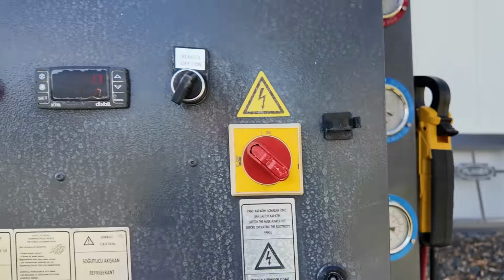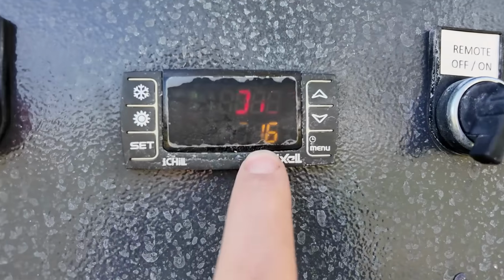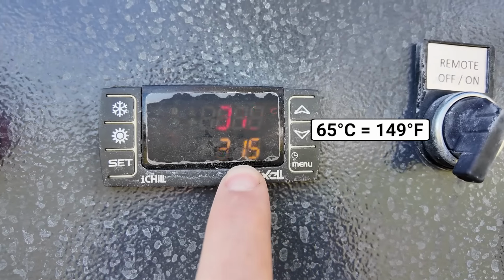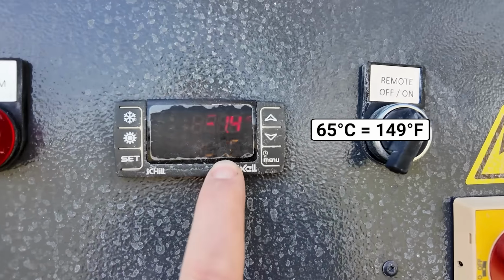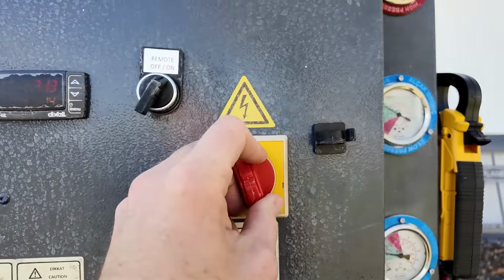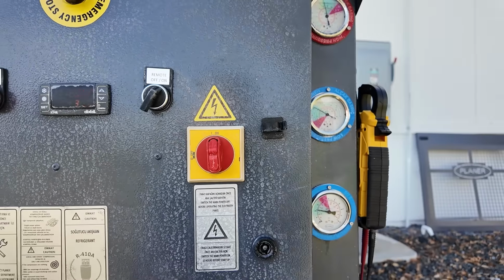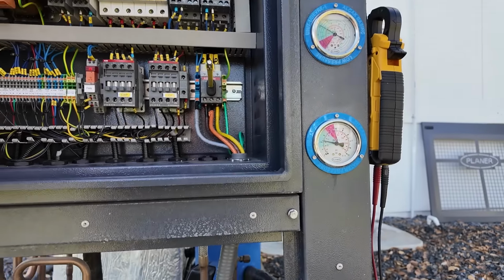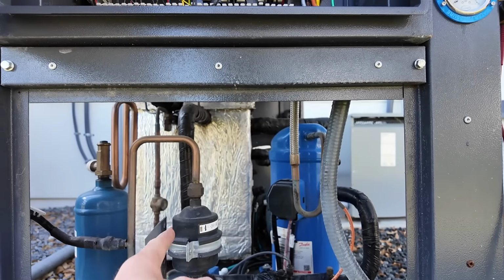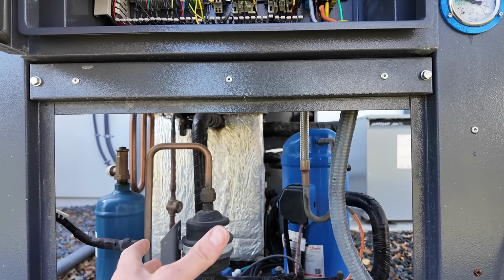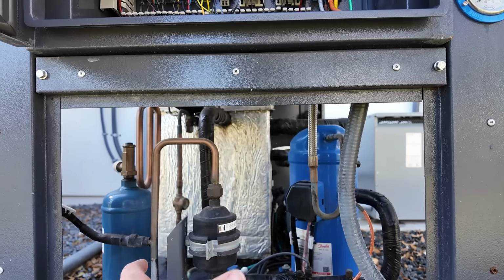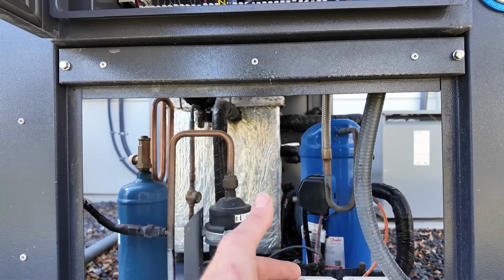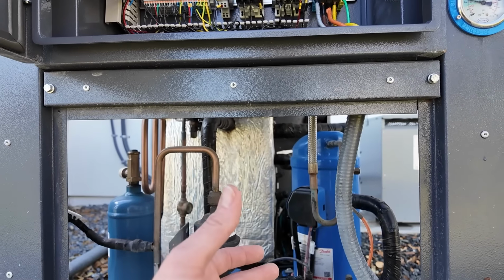Now, when we started with this, our indoor temperature was actually 65 degrees Celsius, which is actually really hot. We've come all the way down to 31 degrees Celsius, which tells me that this system is now running. But here's the thing. When I turned this system on, because this tank was full of hot water, somewhere close to the tune of 150 degrees, it was enough to actually cause my compressor to start to overheat. So I grabbed the water hose to cool down the shell casing.